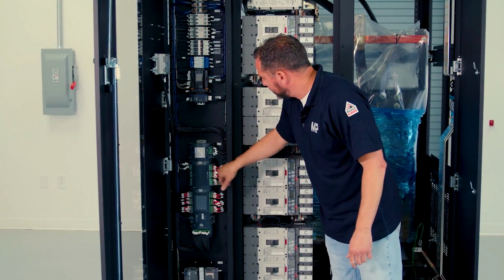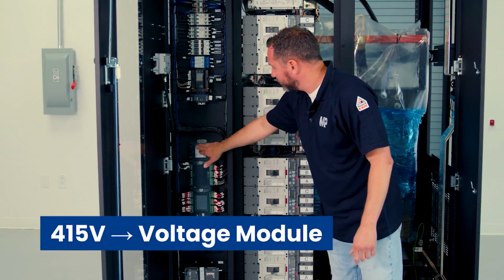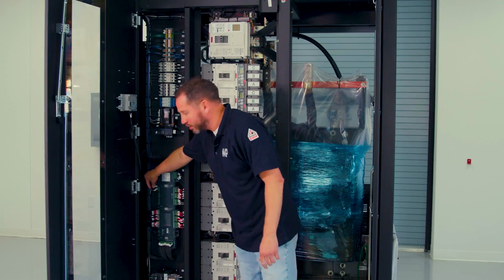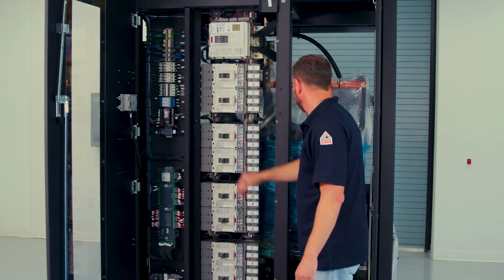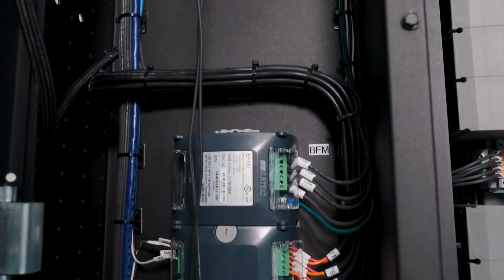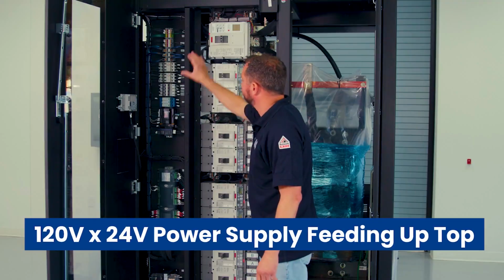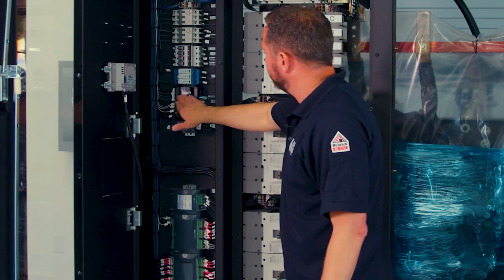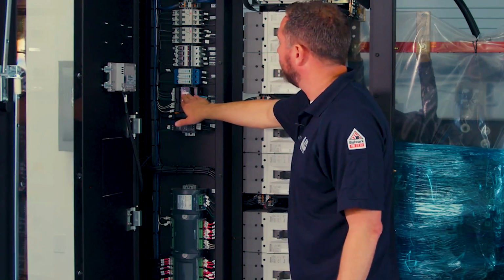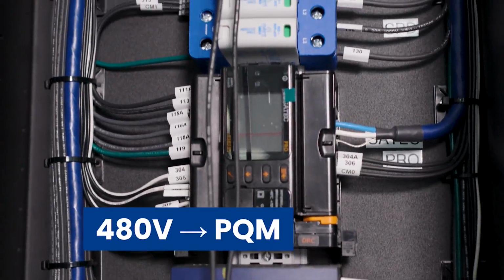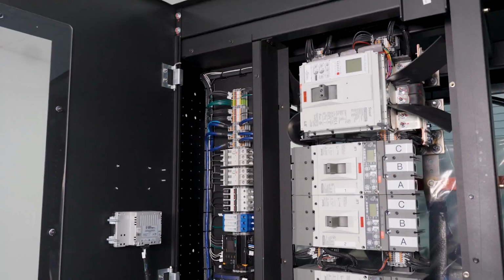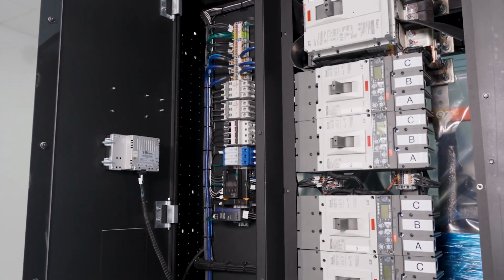On the very top here, we have our 415 coming in to our voltage module. And then we also have our ground and neutral CT on this BFM as well. If we keep going up, as I said, this is our 120 volt by 24 volt power supply feeding up top. Right above that is our PQM. That's our power quality meter. This is our 480 volt coming into this guy. This is all communicating with our main breaker on our primary side of the transformer.